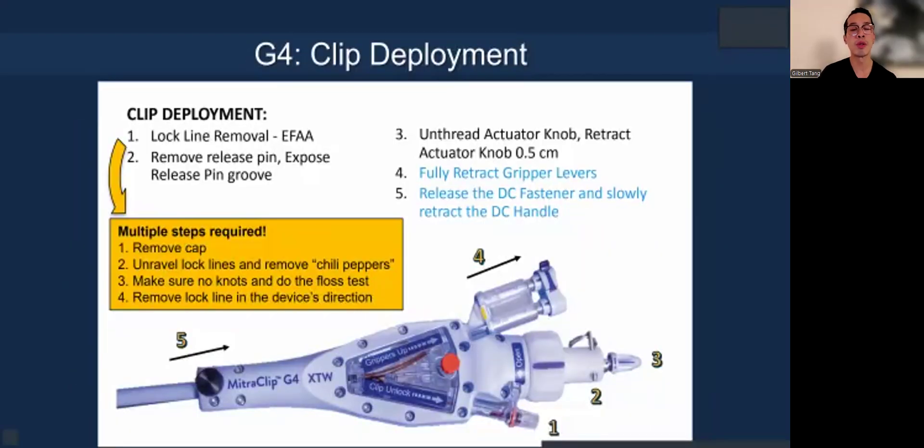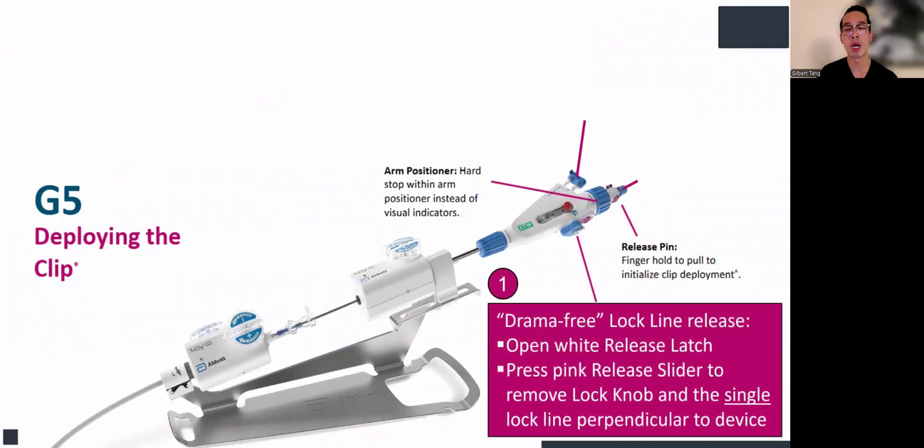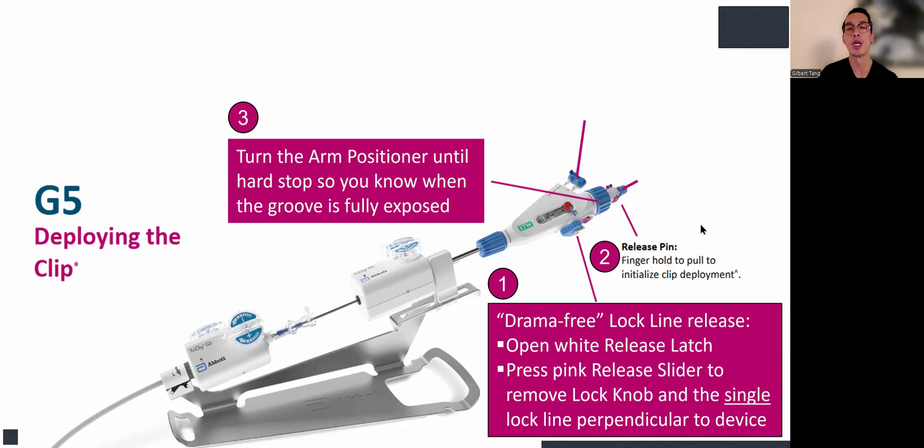How do you deploy the clip? In G4, there are multiple steps required: you remove the cap before unraveling the lock line, remove the two red protective covers, make sure there are no knots on the line, do a floss test, and then remove the lock line in the device direction. With the G5 system, it's much easier — I call it drama-free. You open the white release latch, press the pink release slider to remove and disengage the lock, then a single lock line: you just pull perpendicular to the device and you're done. Then you release the pin and just unlatch it. You turn the arm positioner to a hard stop so the groove is fully exposed — no need to guess how far you're going.